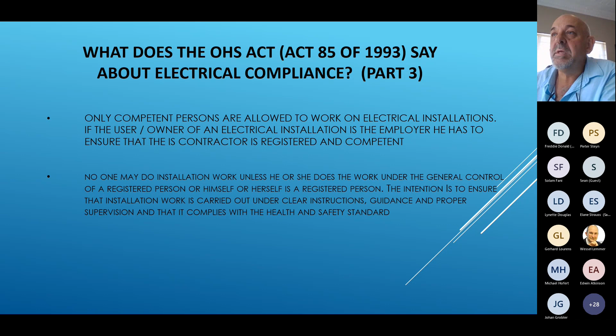The certificate of compliance remains valid until changes are made. What kind of changes, Peter? Well, say we had an incline conveyor or bucket hoist, and we had to replace the motor. We couldn't find the exact same one, so we replaced it with something else, added a support bracket, had to reroute the cable, and the gland didn't fit because the opening wasn't the same. When we collected the motor we found it was a little stronger, so we had to replace the circuit breaker too. All of a sudden you've made changes, and those changes impact the existing certificate, meaning the certificate covering that part of the installation is no longer valid.